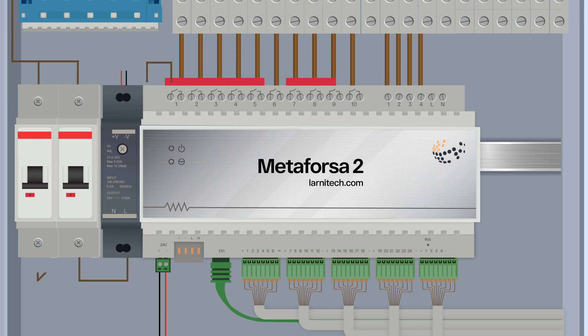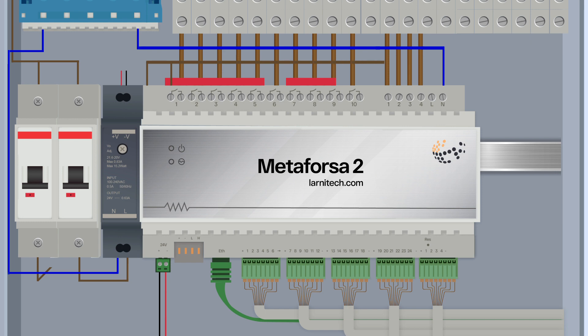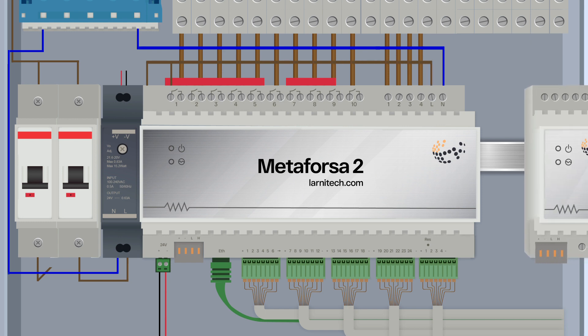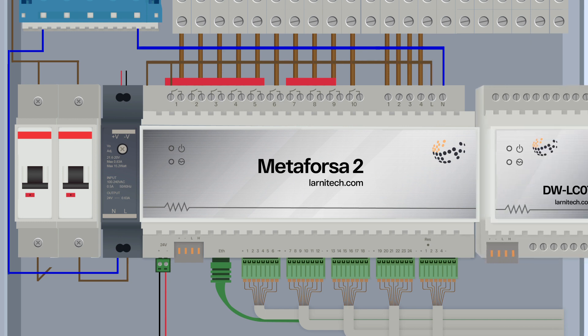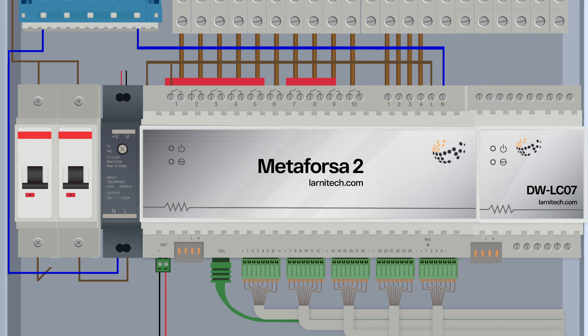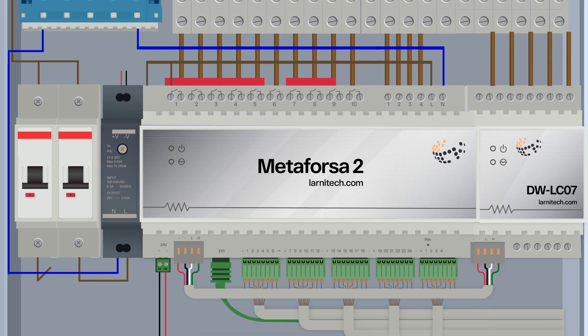We recommend installing two circuit breakers, one for load and the other one for the Metaforsa 2 power supply. If you have extra modules to extend the system, install and connect them, having connected them with CAN bus. Place the terminators at the ends of the CAN bus.